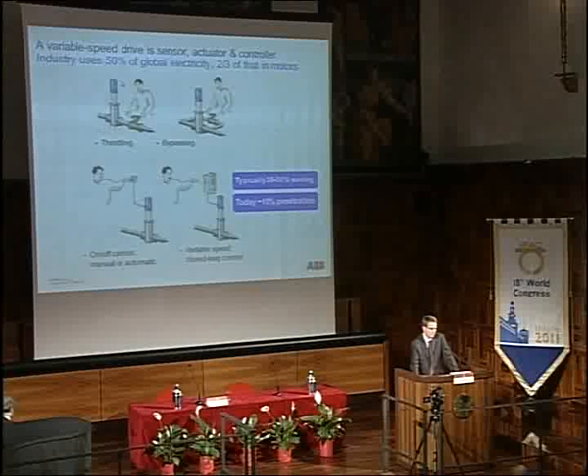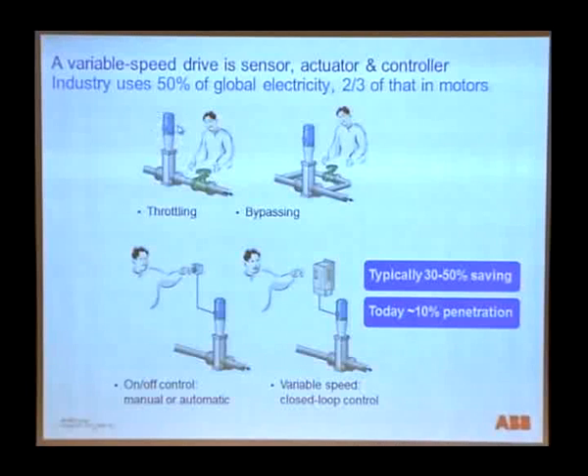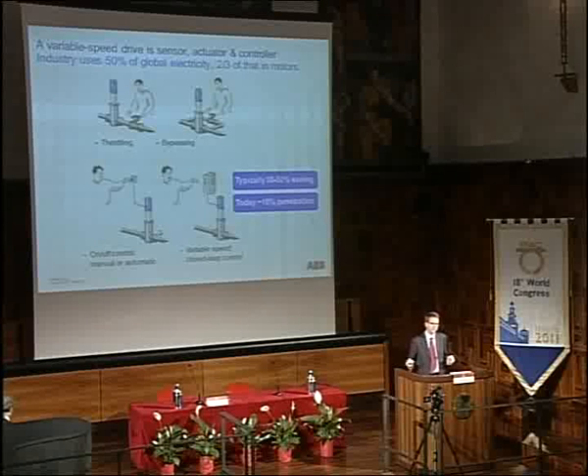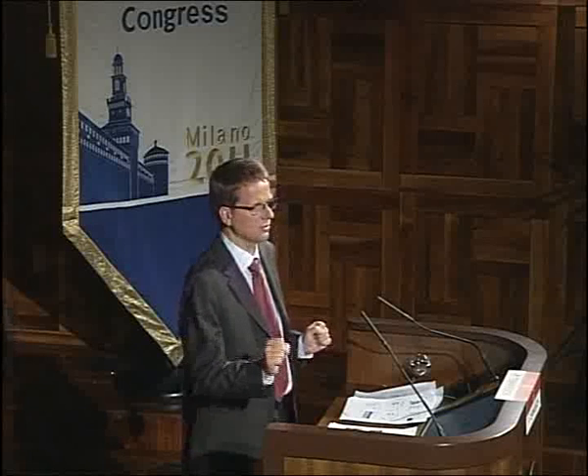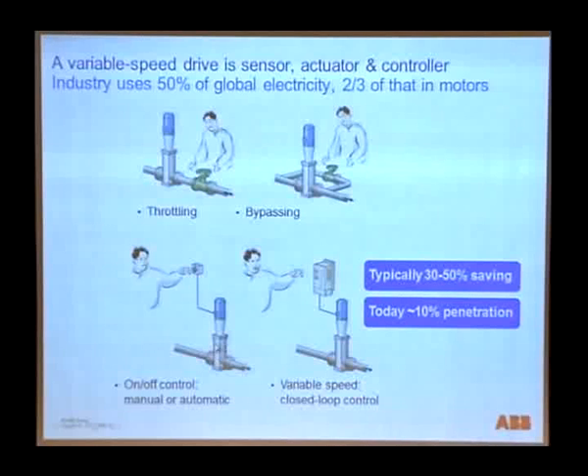If you look at the alternatives, pumping a fluid in a plant, what's often happening is you've got a fixed speed motor with a throttle valve as a way of controlling. From a control point of view, that's not even so bad, you get reasonable control, but it's very poor in energy efficiency, you put the energy in and lose it. There's bypassing, which is slightly better but not a lot. There's on-off control, where manually the thing makes too much flow so you switch it off now and then, which only works if you've got buffers, otherwise it's usually not a meaningful strategy.